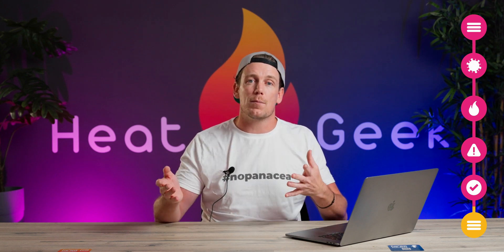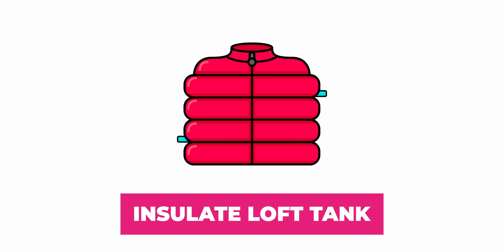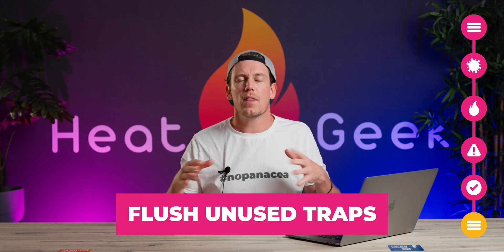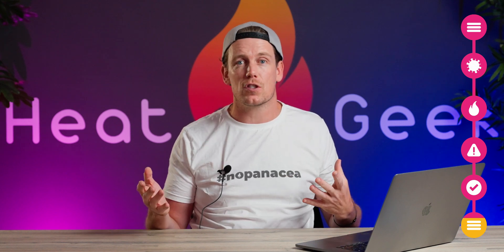Before we go, here are a few extra tips for energy saving and keeping Legionella at bay. Insulate your loft tank if you have one to maintain a lower temperature. If you do have a cold water store in the loft, make sure your cold feeds to the tank and the draw from the tank are at opposite ends to encourage full water turnover. Reduce stagnation by flushing unused traps — that's the water in your U-bends and your toilets — and insulate secondary circulation pipework if you have it. For my own family home, as we turn over around 100% of our stored water each day, I keep my hot water at 45 degrees and I don't do any Legionella cycles. For more energy saving advice make sure you watch our 11 tips on saving energy. If you've enjoyed this video, hit like, comment if you agree or disagree with anything, and subscribe for more content.